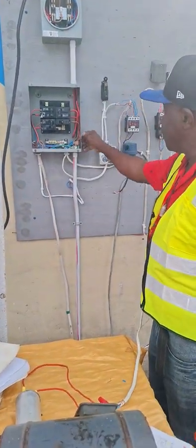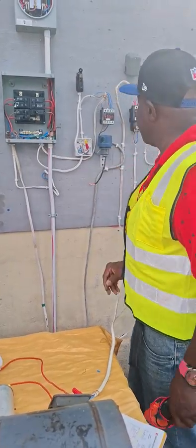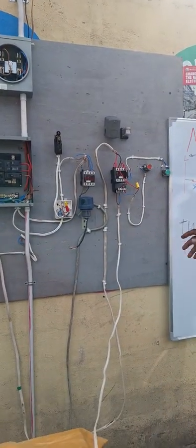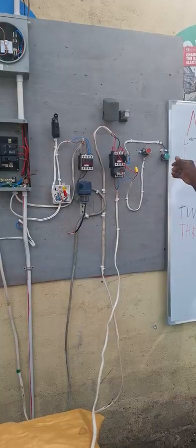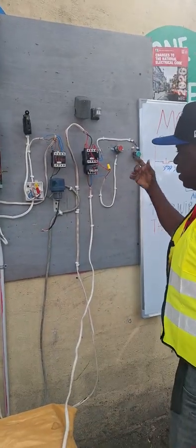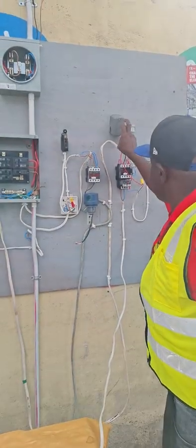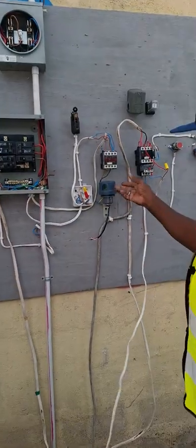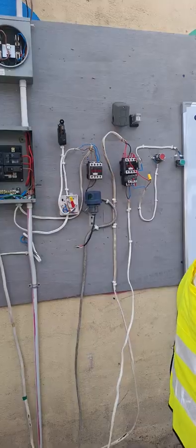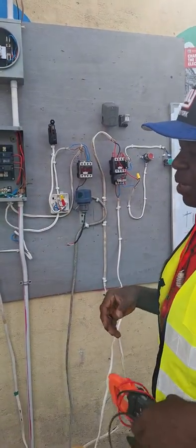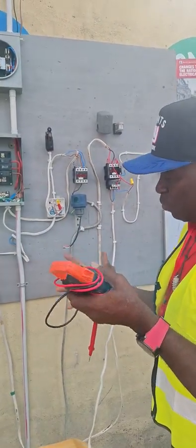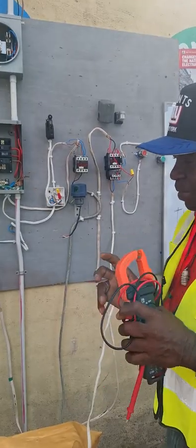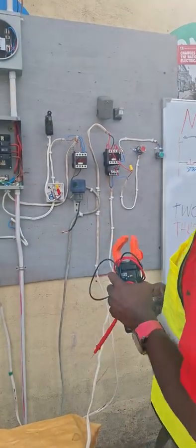So here is my circuit, a demonstration of a distribution panel. Ensure that my panel distribution board is properly grounded and bonded, as I say. We have two sets of devices. We have the input device, which is the pilot device, which would be the switches. This is a pressure switch for a water tank. This is a limit switch. A photocell could also be an input device, and a float switch, a flow switch, a pressure switch, a thermostat. All those devices we consider as input devices, or pilot devices.